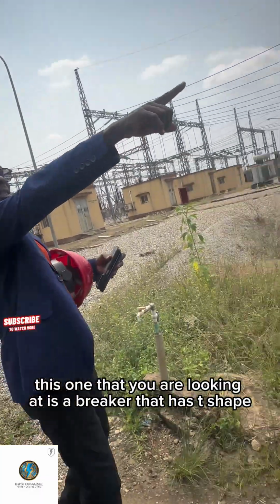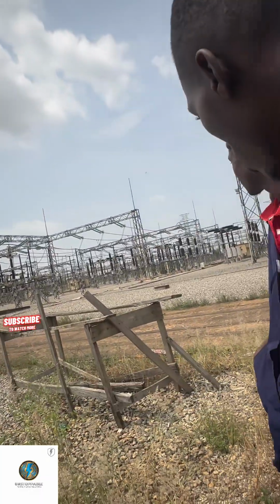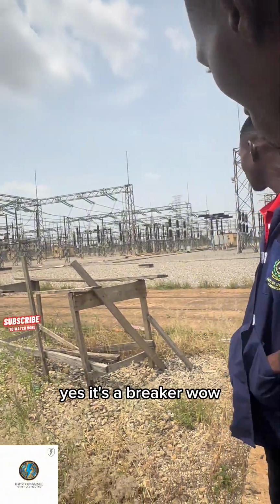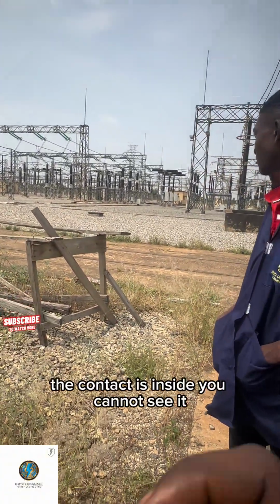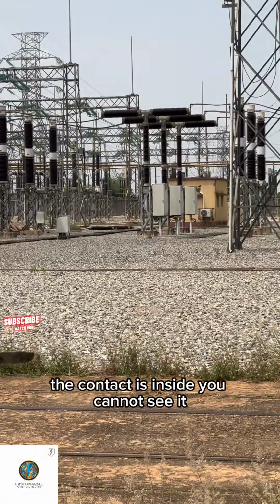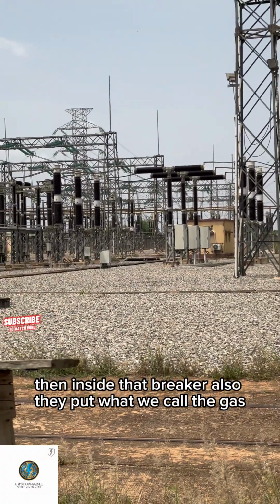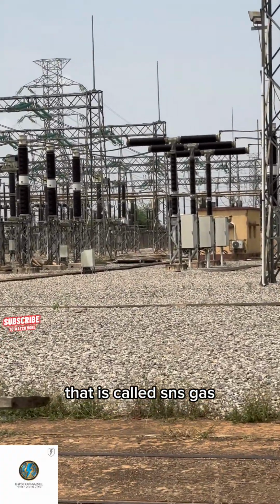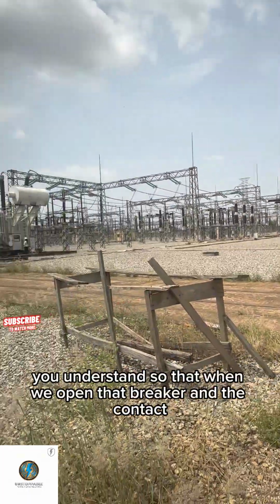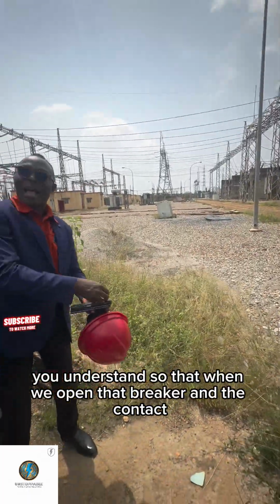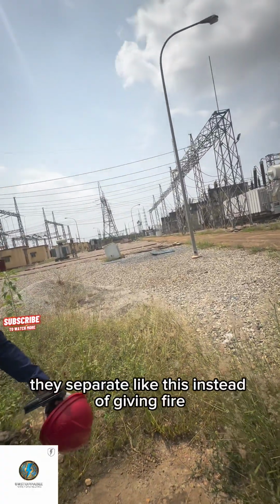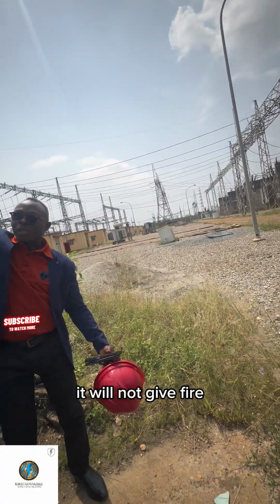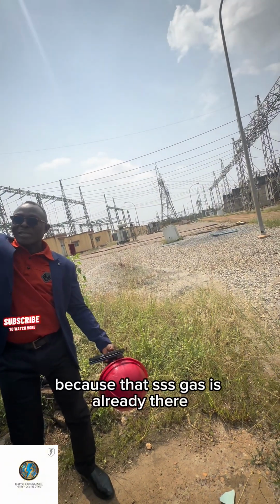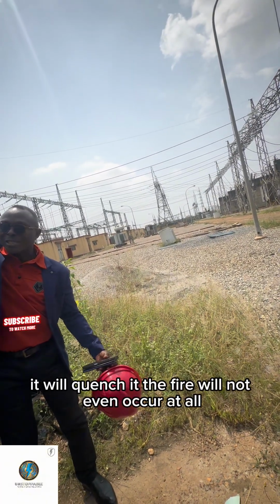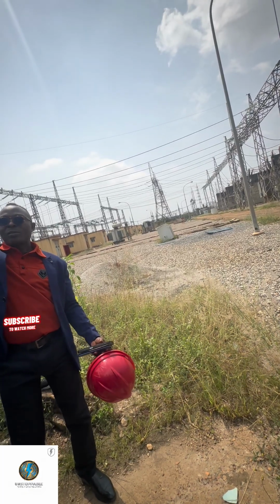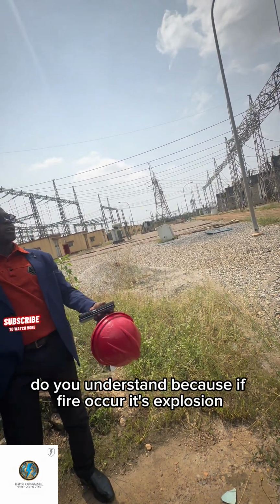This one that you are looking at is a breaker that has a T shape. The contact is inside. You cannot see it. Inside that breaker they put what we call the gas, SF6 gas. So that when we open that breaker and the contacts separate like this, instead of giving fire, it will not give fire, because the gas is already there. It will quench it. The fire will not even occur at all. Because if fire occurs, it's an explosion.